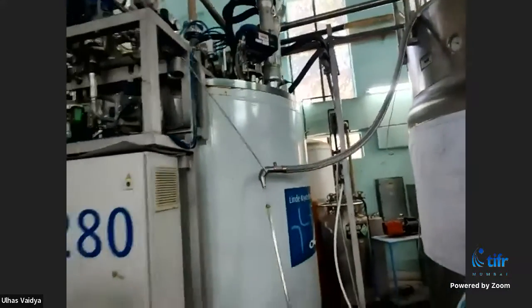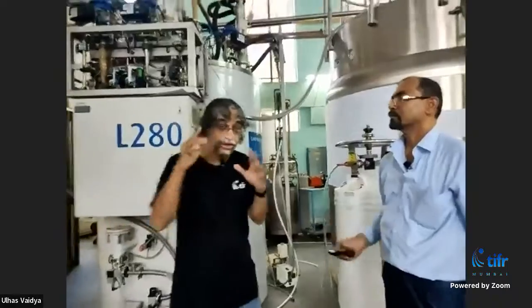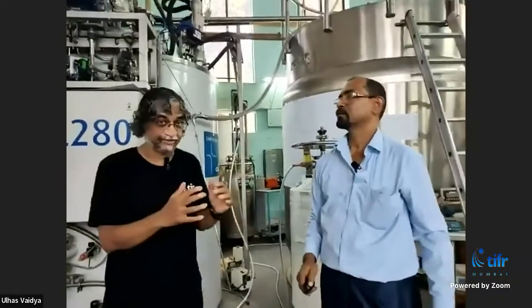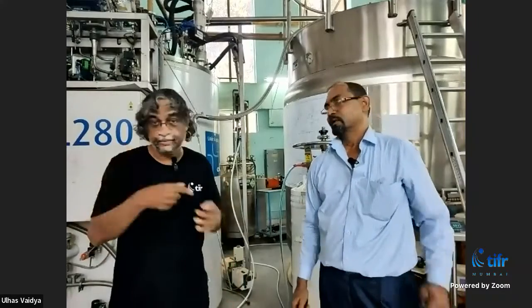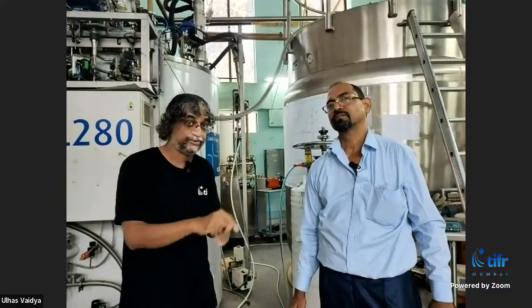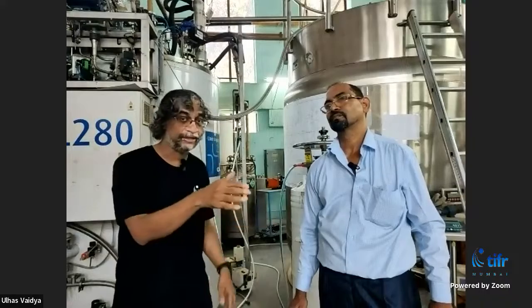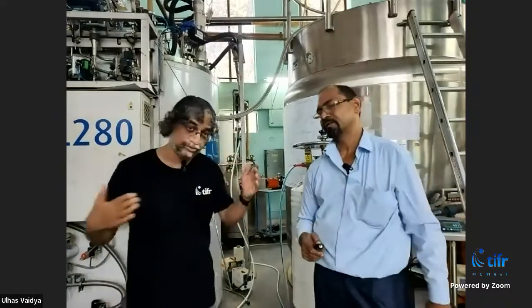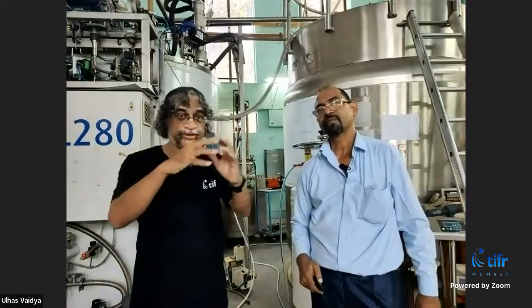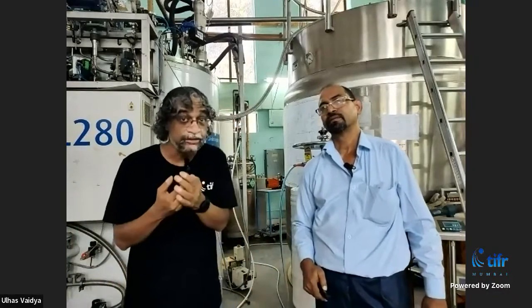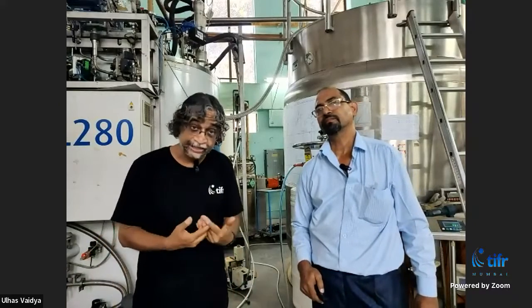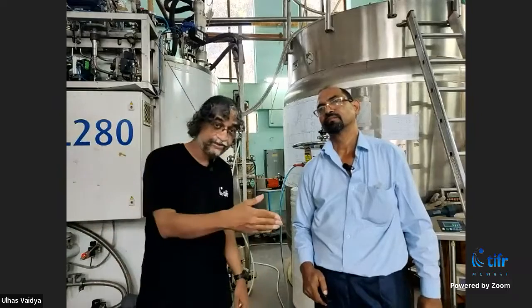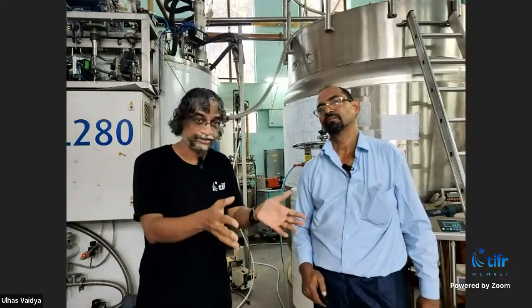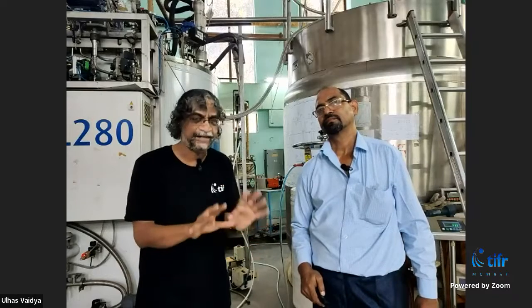Let's start with the compressor. But first, let me tell you what happens in the turbine expander, because that's the heart of the system. It has blades rotating extremely fast, about 200,000 times a minute. The gas molecules move randomly, but when they hit these fast-moving blades, they get knocked tangentially, pushed from a high pressure region to a low pressure region. That's how expansion happens, and that's how you get cooling. This works for helium too - the molecules get hit by the blade, gain velocity, and are thrown toward a region of low pressure. That's how the turbine expander works in simple terms.